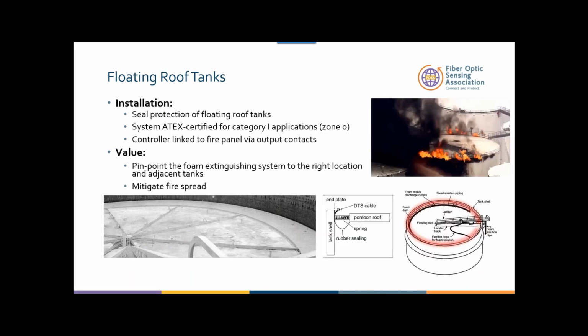Floating roof tanks is an example. This is a very, very good approach of using fiber optic linear detection, because we are not just a detection system, we also can tell you if you're overheating. In this case, on the right, you can see there's a fire on the right-hand side, and then this tank is on fire, but it's also affecting the other tanks. If this tank is burning so much, this tank will take over as well, and then start burning as well.